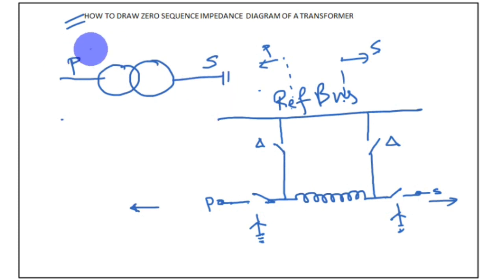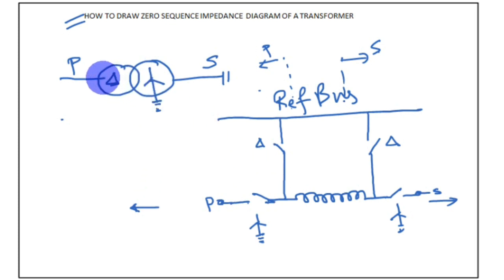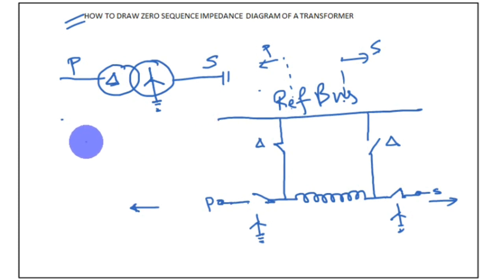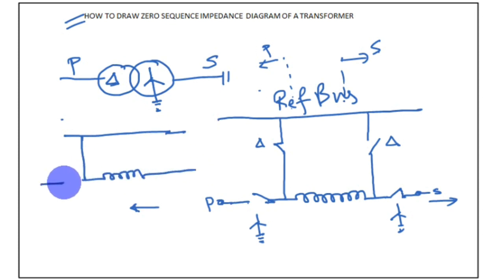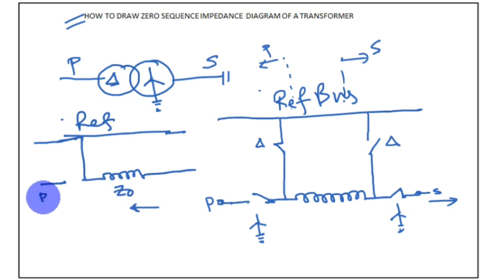For example, consider a delta-star transformer — delta on the primary and star with neutral grounded on the secondary — which is a very common transformer used in industry. The primary side is delta, so we close the primary switch. The secondary neutral is grounded, so that switch also closes. The resulting zero sequence diagram shows an opening on the primary side but a continuous path on the secondary side, meaning zero sequence current will not pass to the primary side when an earth fault occurs at the secondary.